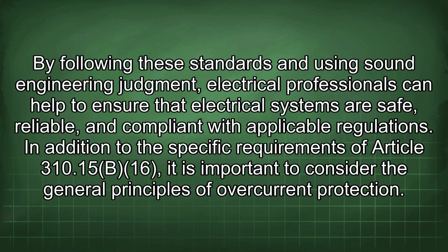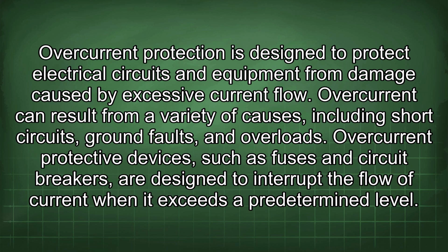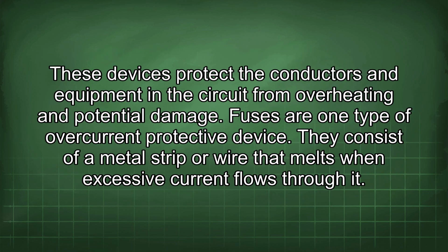In addition to the specific requirements of Article 310.15(B)(16), it is important to consider the general principles of overcurrent protection. Overcurrent protection is designed to protect electrical circuits and equipment from damage caused by excessive current flow. Overcurrent can result from a variety of causes, including short circuits, ground faults, and overloads. Overcurrent protective devices, such as fuses and circuit breakers, are designed to interrupt the flow of current when it exceeds a predetermined level. These devices protect the conductors and equipment in the circuit from overheating and potential damage.